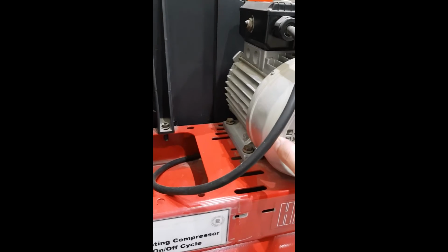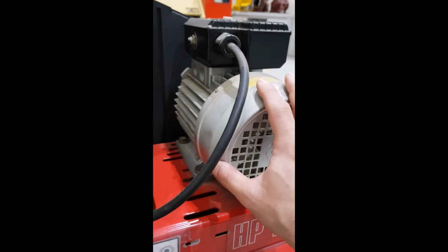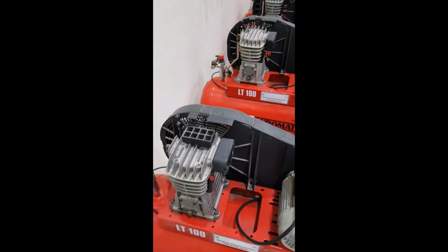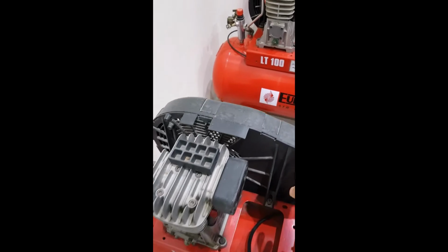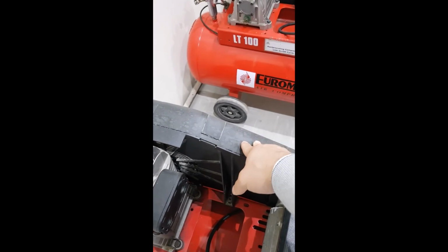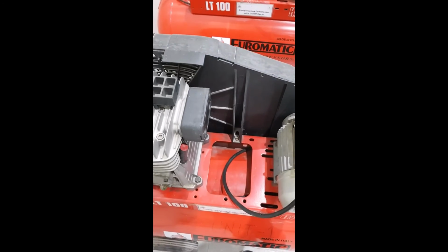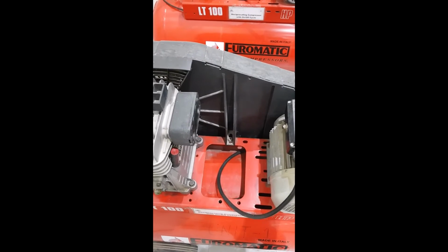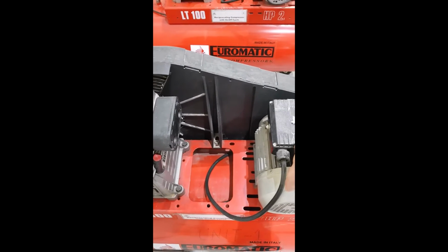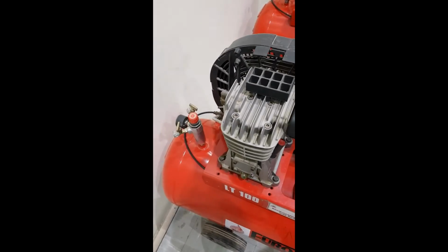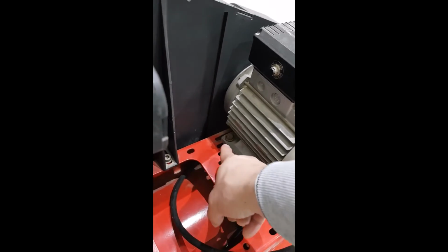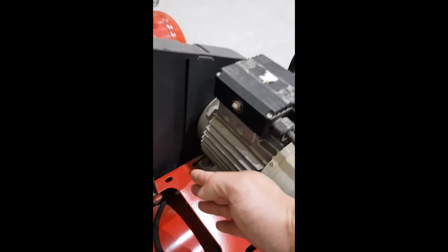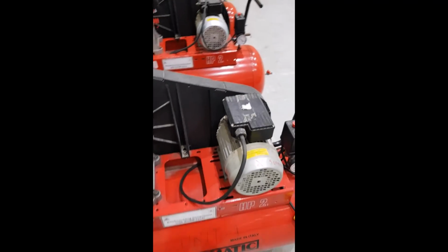Remember, an important point: one of the routine maintenance tasks that needs to be carried out in this area is to check the tensioning of the belt, as I showed you in the class. If the belt is too tight or too loose, the only part that moves in the whole set is the motor. You can remove the bolts over here and shift it right or left for tightening or loosening.